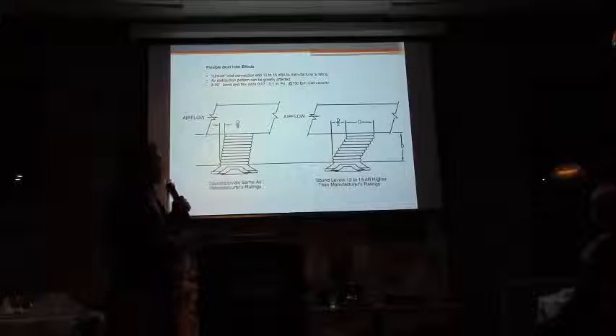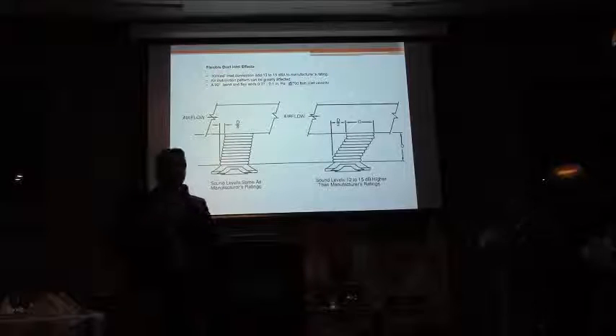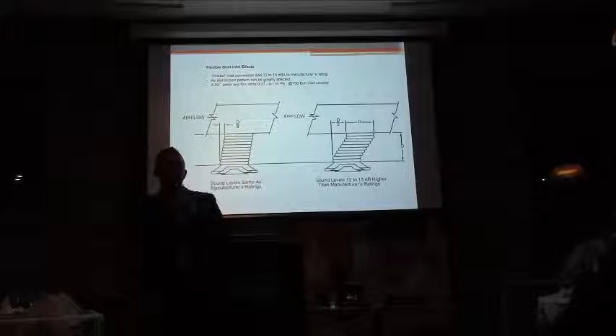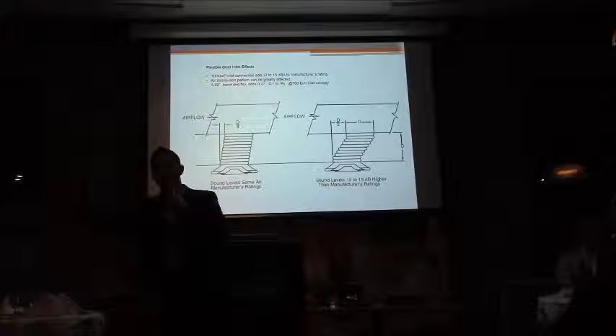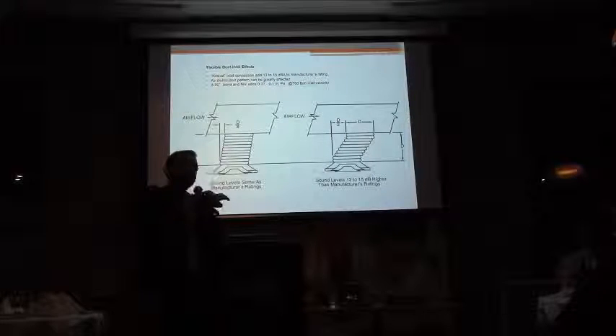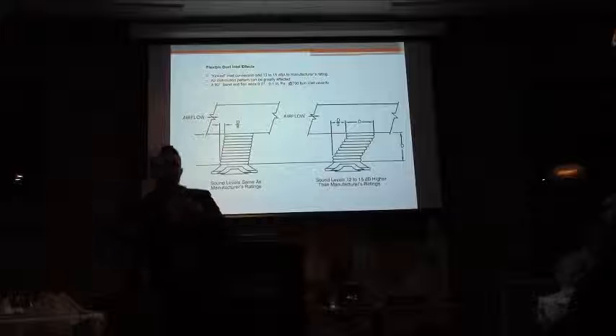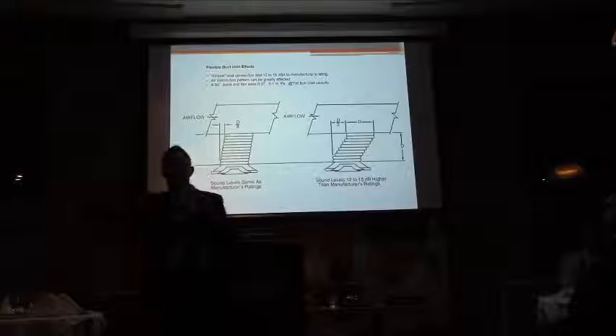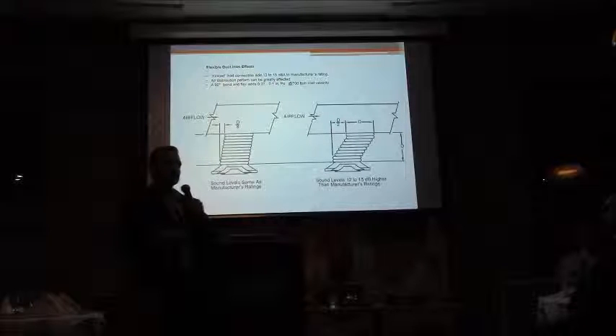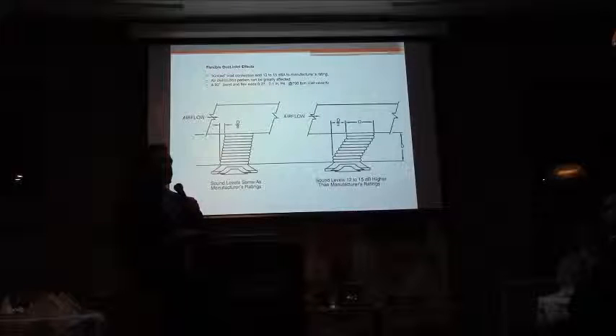The air distribution pattern can be greatly affected. So what that means is that whenever you read a throw, and it says, for example, 8 feet, that's based on it being symmetric on both sides. So you get 8 feet of throw on one side and 8 feet on the other side. But if you're using a flexible connection, you're coming in horizontally, and the air doesn't have time to stabilize before reaching the diffuser, you might get 80% of the air going one way and 20% going the other way. So whatever throw calculations you did at the design phase are not really working anymore in the field, just because of the flexible duct connection.